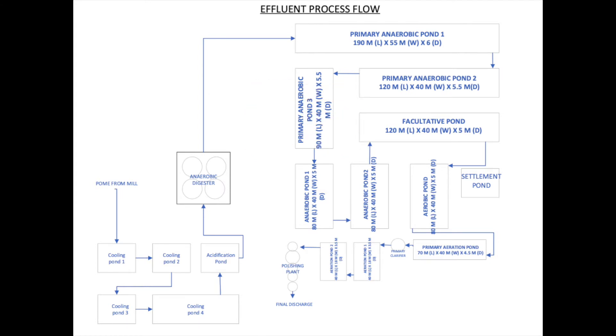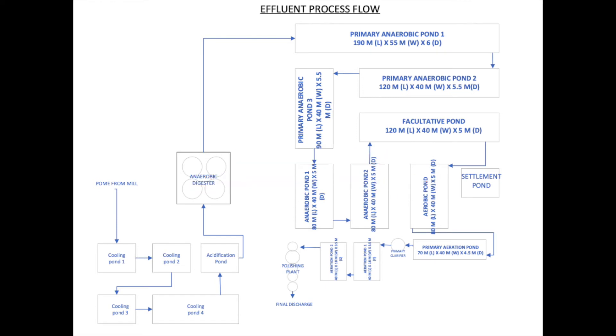The average final discharge BOD for the last six months was about 100, going down to as low as 50. From the schematic, you can see that some of the flow process is not optimal.